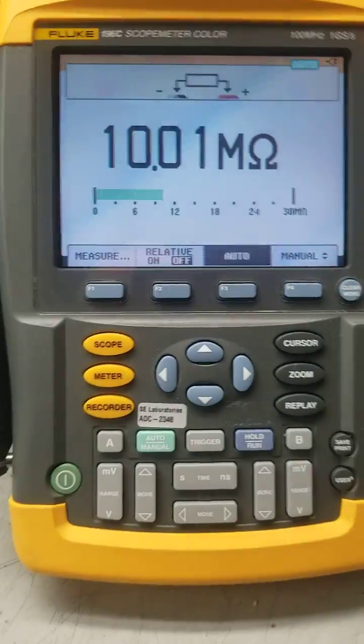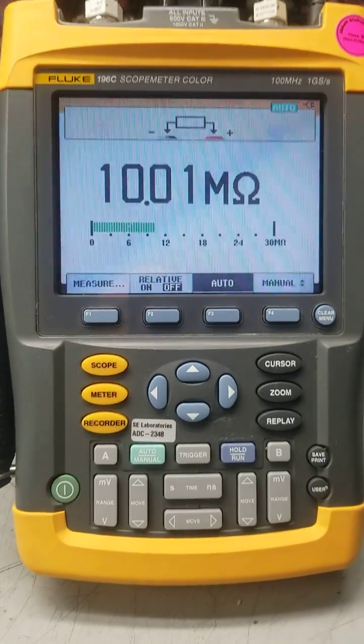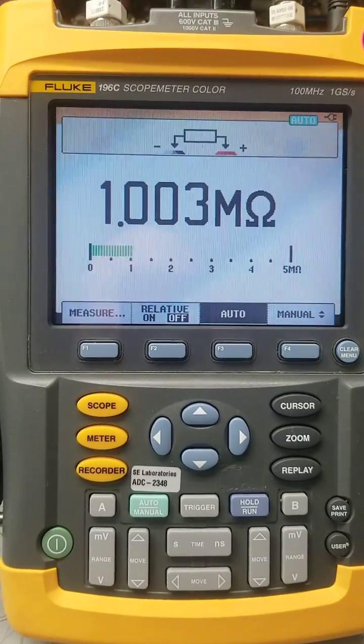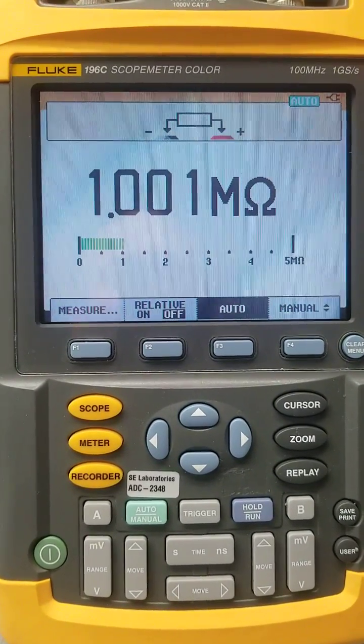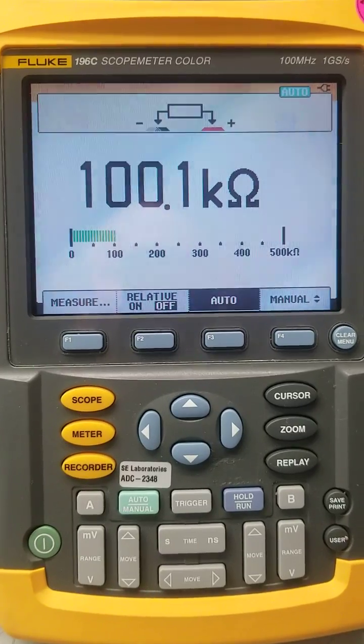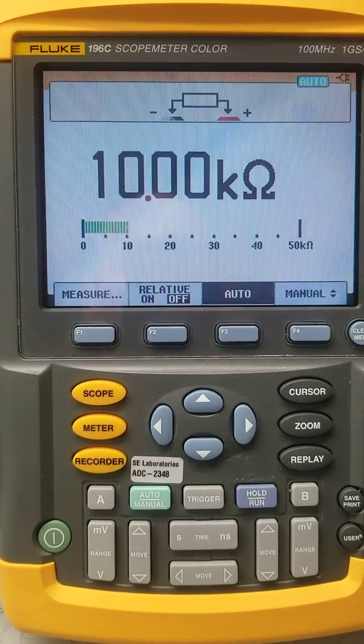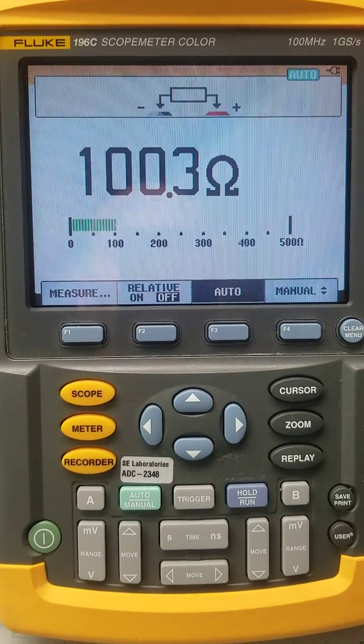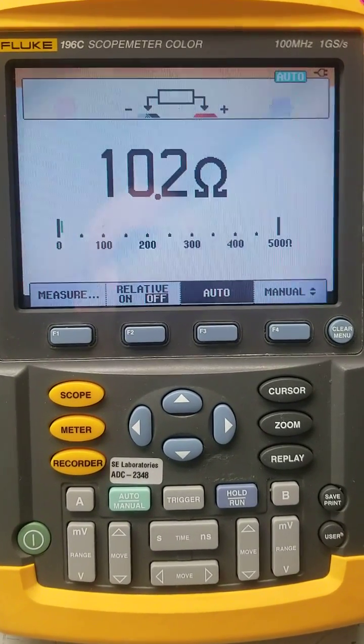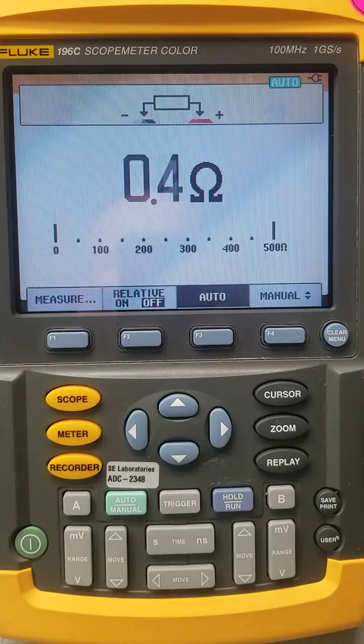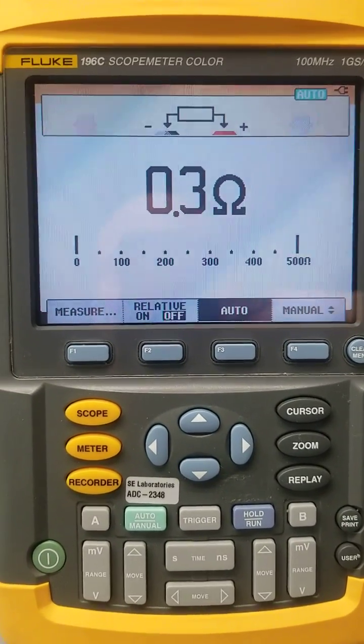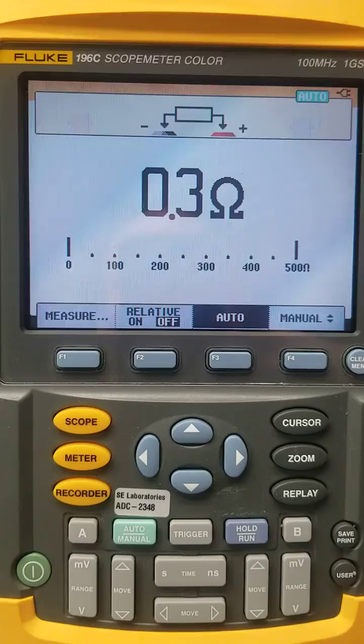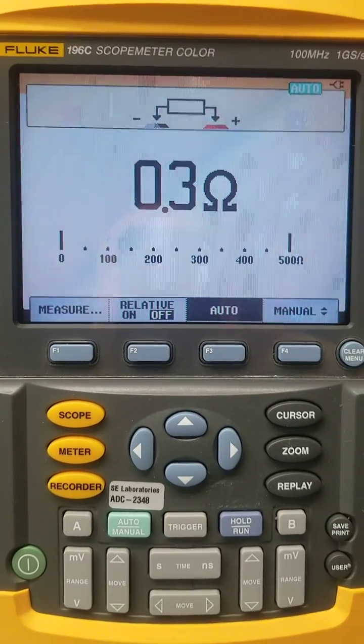Okay, so here we go. Right now we are applying 10 mega ohms from the calibrator. I'm going to go down in the ohms. It's a short and you can see the leads measure 0.3 ohm, so there was no error on lower ranges. It's due to the leads resistance.